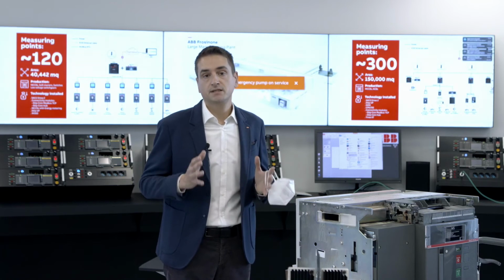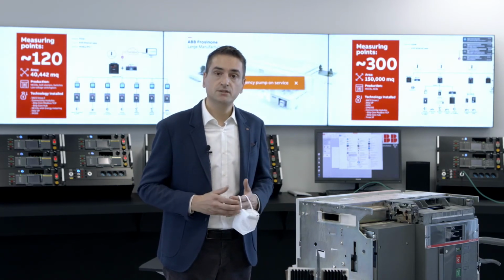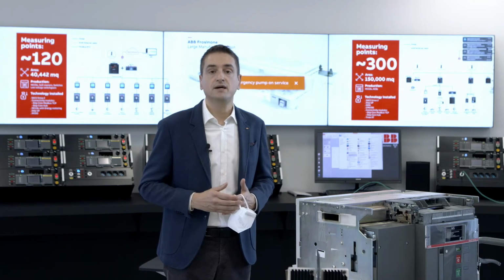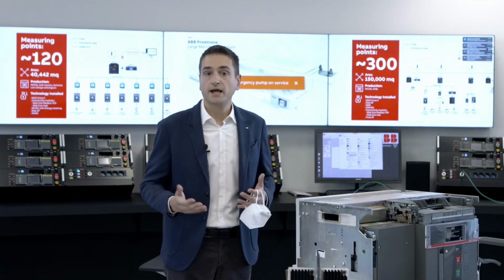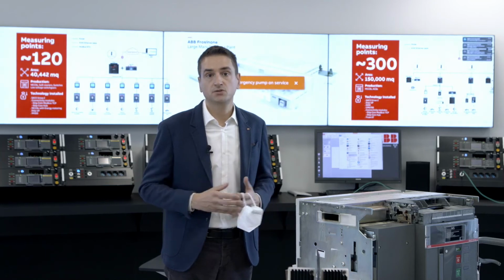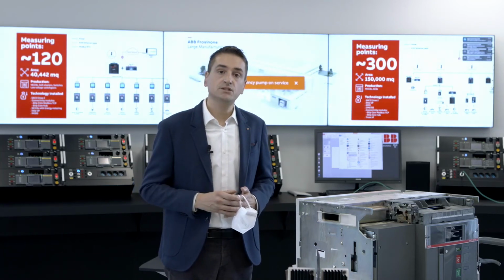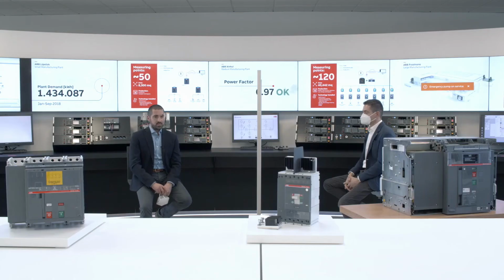E4.2 MSDC is the complete solution of switch disconnector up to 1,500 volt DC for applications like photovoltaic, energy storage solution, and many other DC applications. With MCCB, we can cover application up to 1,500 volt in DC at 200 amps with a circuit breaker according to UL 489B and F, and up to 1,200 amps for the switch disconnector according to UL 489B.